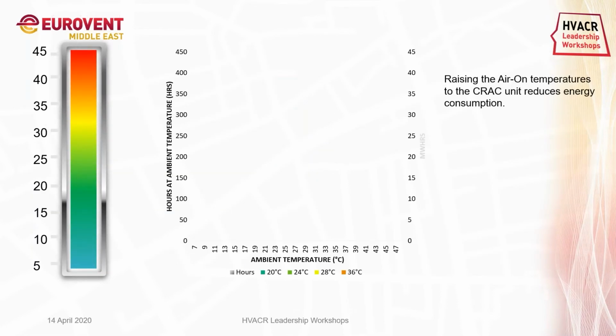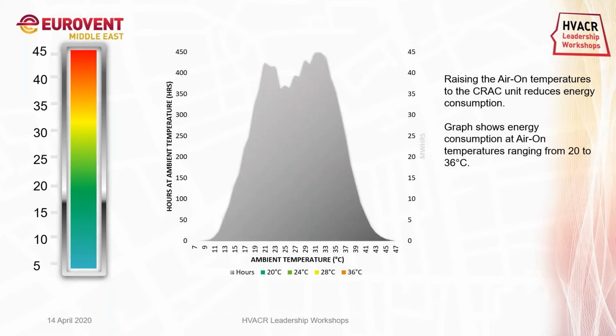Now, as you know, raising the air temperature reduces the energy consumption. The higher the return air temperature, the higher the capacity, or in other words, the higher the return air temperature, we can select the lower models of the CRAC units. The graph is about to show energy consumption at air-on temperatures ranging from 20 to 36 degrees Celsius. This is the ambient temperature plotted in hours, which were measured in Dubai actually. At a set point of 20 degrees Celsius, you can see the energy consumption in the green.